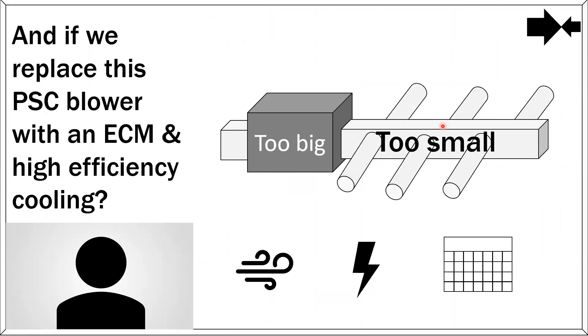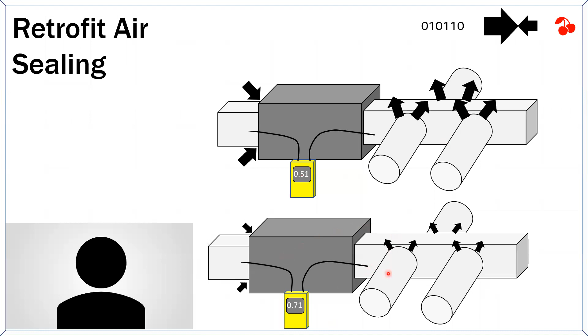And one of my favorite ones is when you go in and air seal a leaky duct system. Cool. All that air leakage, you know what that's called? Pressure relief. It's not a good thing. I don't want it, right? Remember the very first slide. I'm not advocating leaky duct systems, but you go in and seal them up and you don't look at the duct sizes and you don't look at the amount of airflow you're putting into it. You're going to increase the static pressure on your fan, and that can have some huge negative consequences.